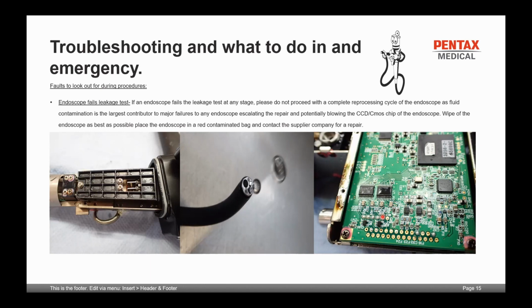So 9 times out of 10, the damage is going to occur during a procedure. While the endoscopist is utilizing the instrument, perforation of the instrument channel or a needle passing through and damaging a channel is very possible. But what happens is the leak goes undetected, and the cleaning and reprocessing sisters continue with the reprocessing of the endoscope, which in turn causes fluid inside an electronic device, which does not go well together. So sometimes a small, simple repair like this, which is just an instrument channel replacement, going undetected, turns into severe fluid contamination and possible PC board and CCD damage because it wasn't detected before they started the reprocessing of the scope.